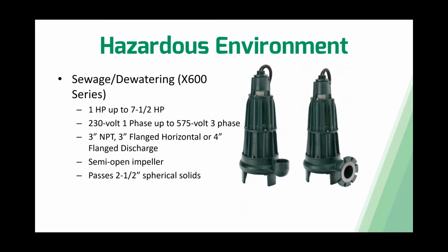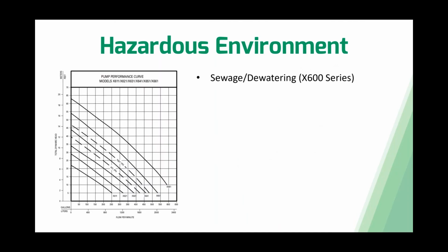Whereas on a semi-open impeller, the fluids and the solids or whatever's going through it must pass through the impeller vanes, which means the vanes of the impeller are coming in contact with the fluid or with the waste or with whatever's coming in contact with it. And then you always have, if there's a lot going on, you may see potential clogging or jamming when you use semi-open versus the vortex impeller. But just know that when it comes to these X600 series, it can pass large solids, like 2.5-inch spherical solids. So if you take a look at this pump performance curve for the X600 series, going up from the X611 up to the X661, you'll see a variety of pump performances, many different total dynamic head options.